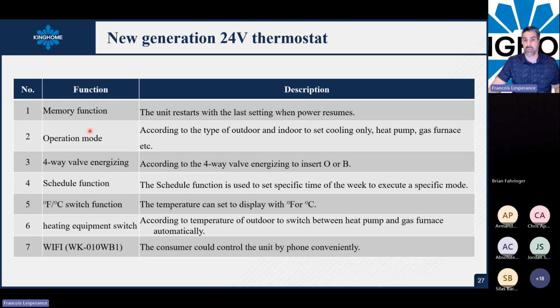You will have the memory function, all the operation modes. The reversing valve can be set depending on which connection you use. O activates cooling, but for our model, we're using B because the reversing valve is active in heating mode. You can do some scheduling. You can use Fahrenheit or Celsius. You can adjust your outdoor balance point also by using the Wi-Fi. You will have the temperature and all the stuff.